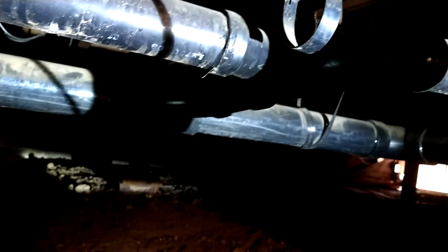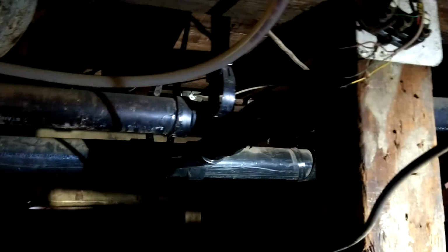I'd like you to send it to him, and I'd like you to CC me so they know that it's been done. Again, that's something that the owner needs to follow up on, or you need to follow up with the building division. And you can see here too that that's supposed to be a strap for the pipes, and it's not strapping the pipes. The pipes are not in the strap.